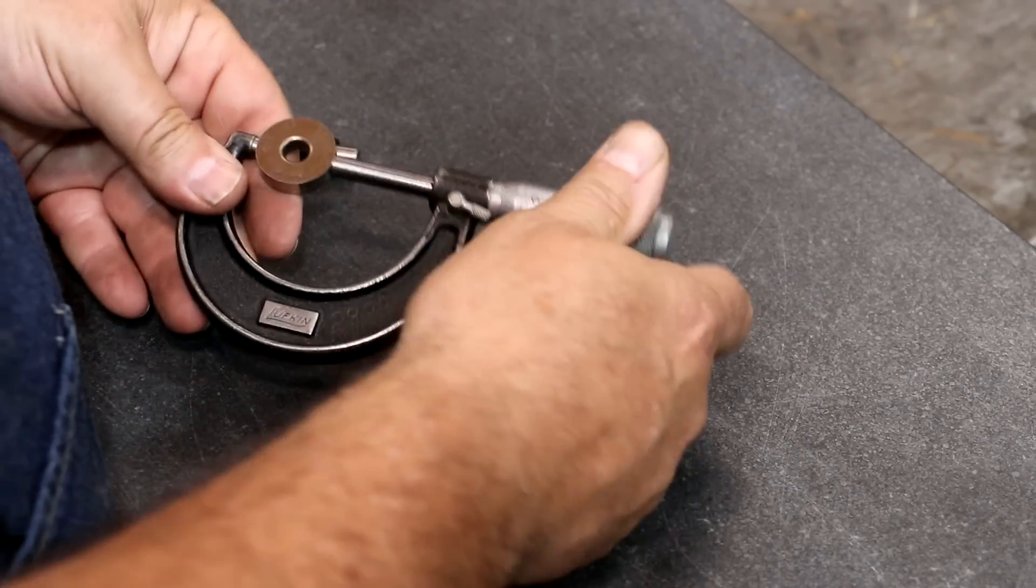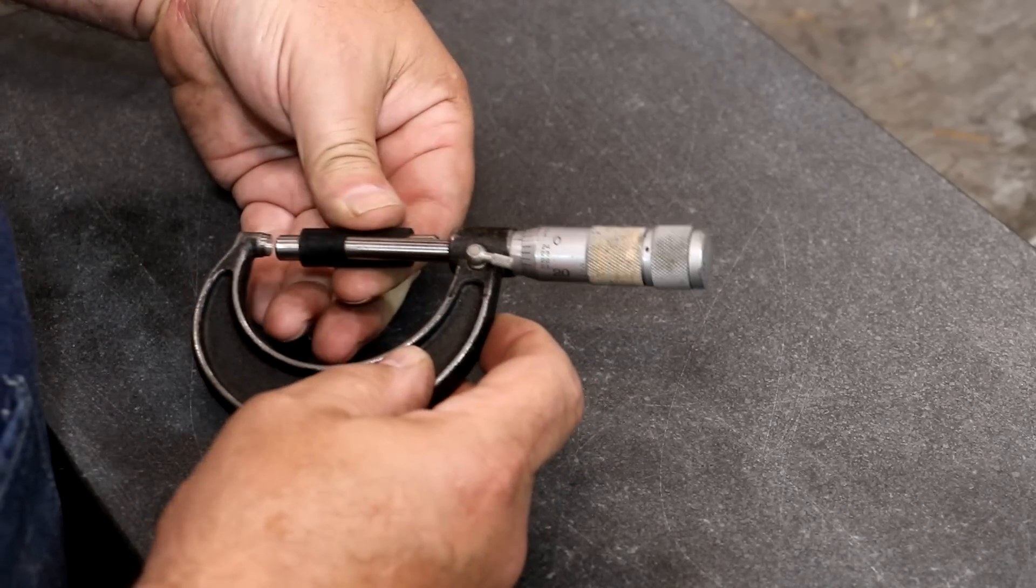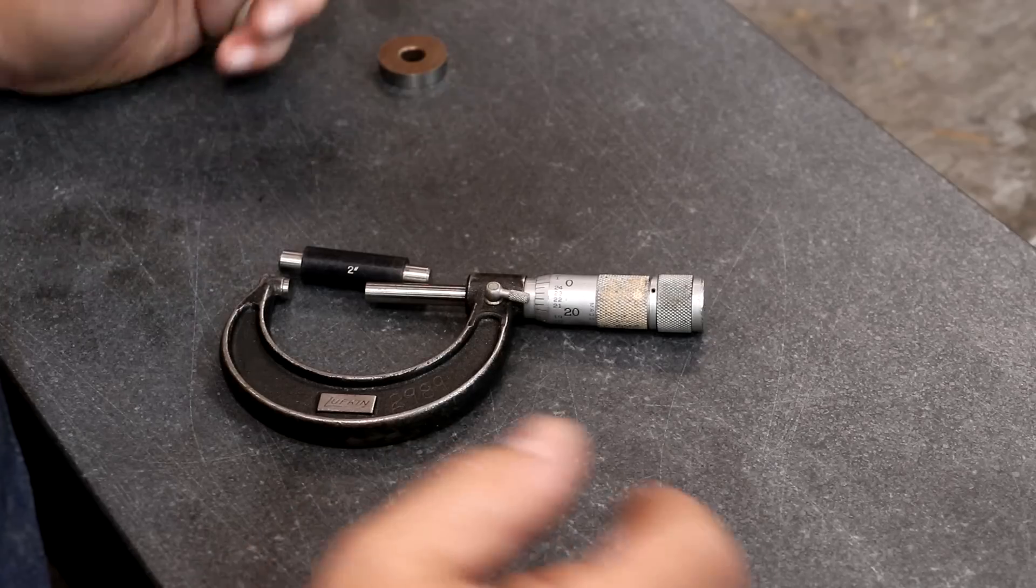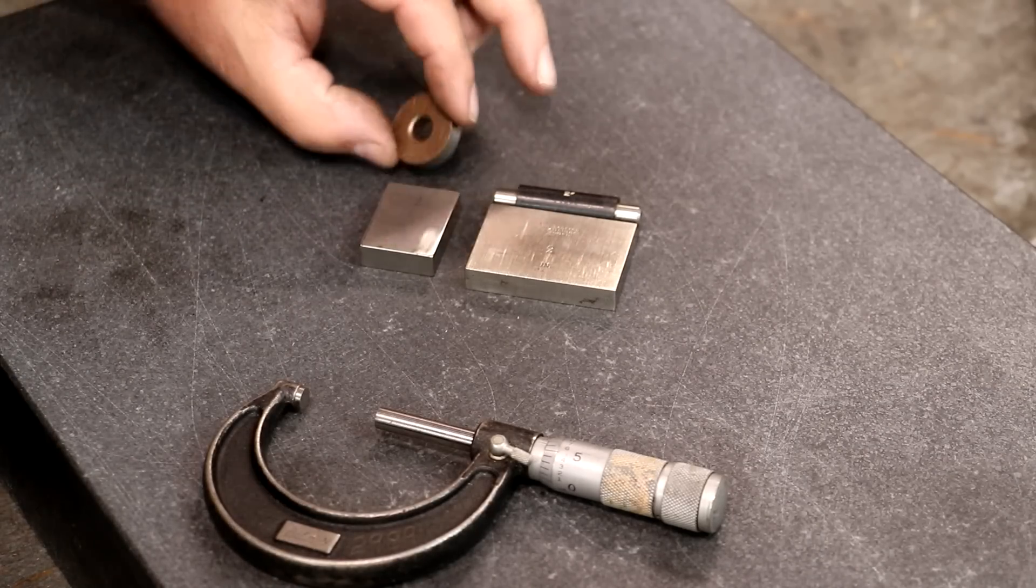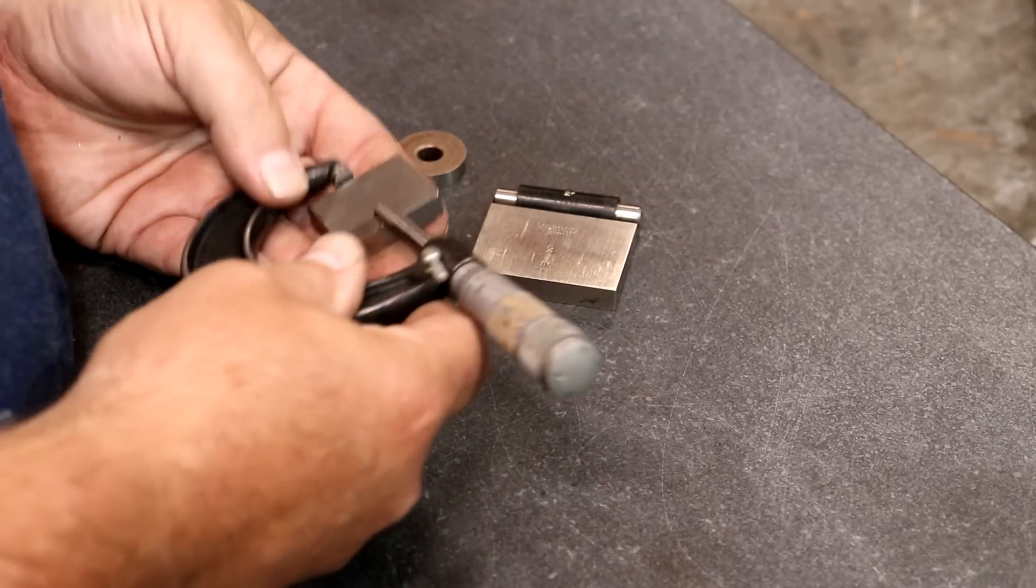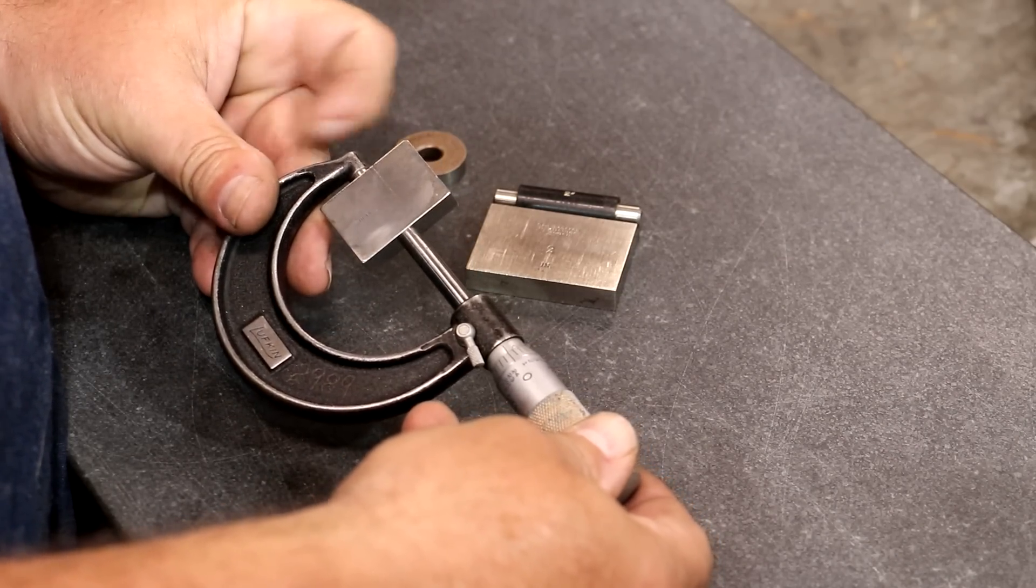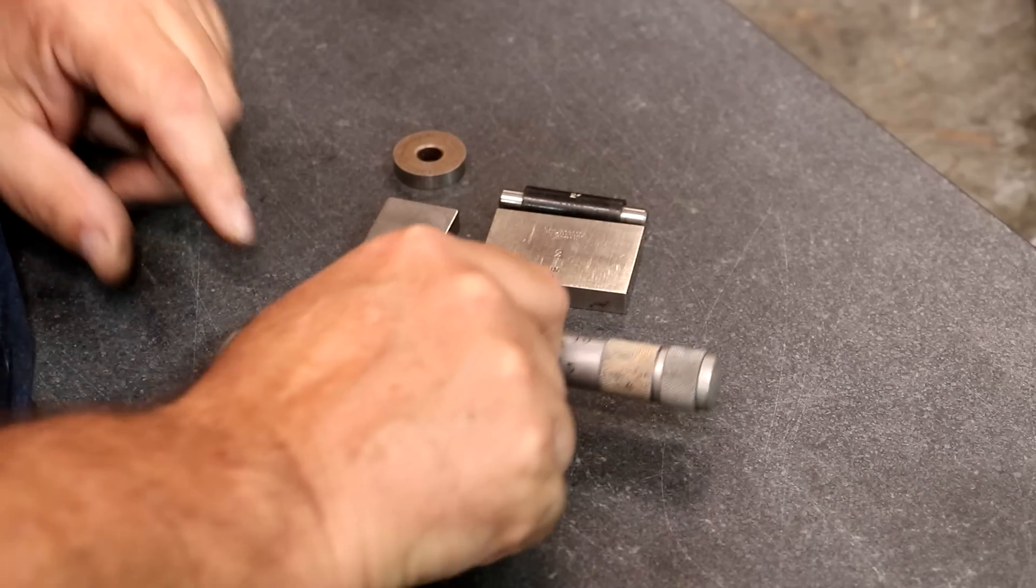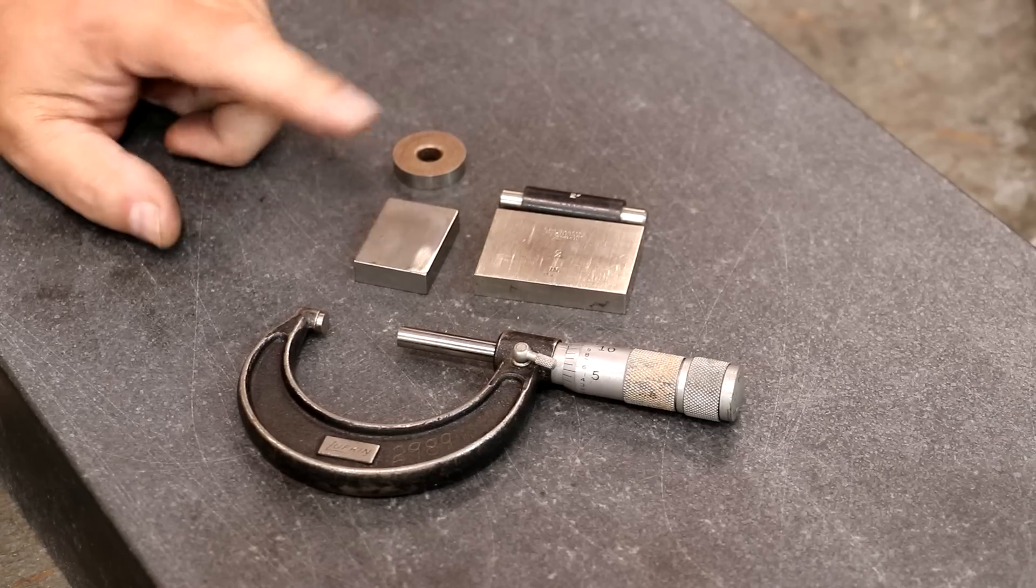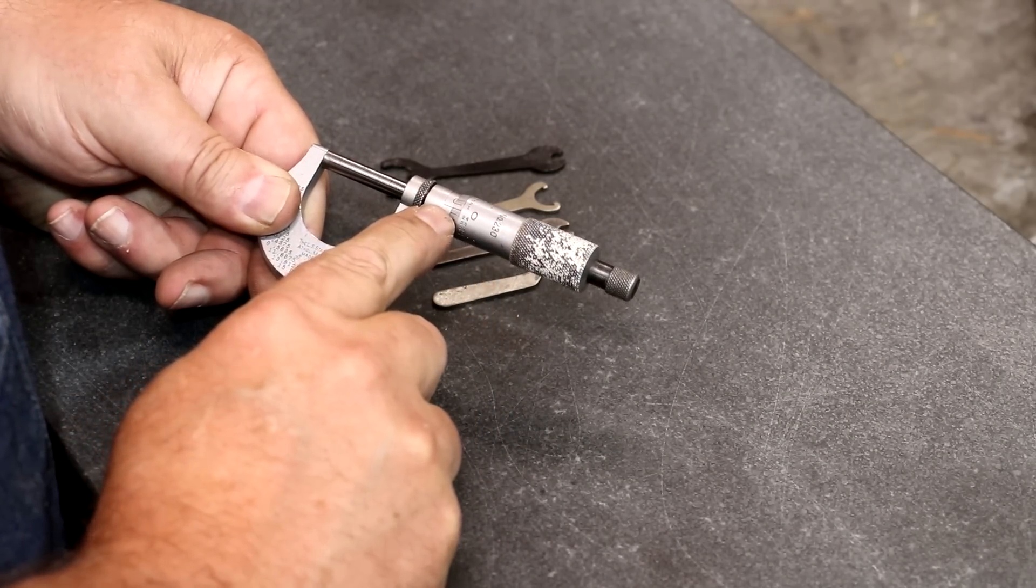Now, if I wanted to, again, I could check the other end. Normally that's not done on micrometer standards. When you get to the larger ones, they typically go to something like this. And that standard is exactly two inches long. Now, if you don't have micrometer standards, you can use gauge blocks for this. A lot of people may have gauge blocks. So if you don't have the standards for micrometers, you can use these gauge blocks. These gauge blocks are fairly standard in machine shops and whatever as standards for checking all kinds of things. And you can see there, my one inch gauge block measures one inch, and I got two inch here as well that we can use if needed. It's the exact same length as this. This is just a known standard. So as long as your gauge blocks are in good shape and measuring accurately, you can use these as well.